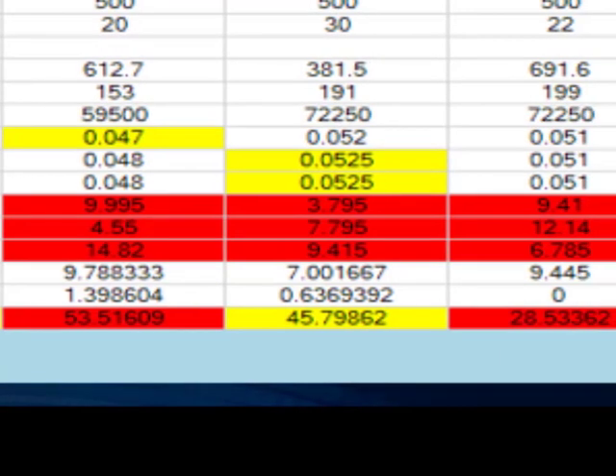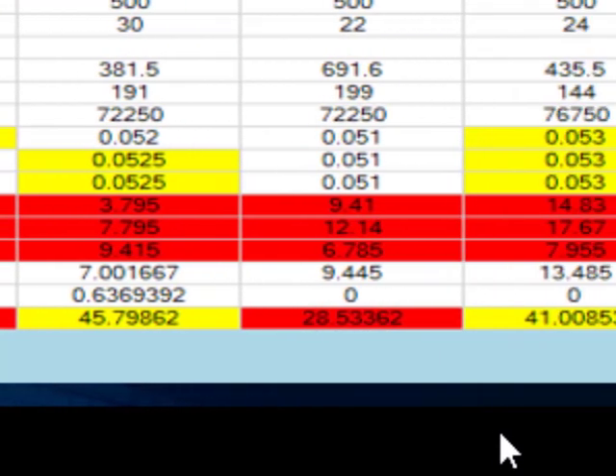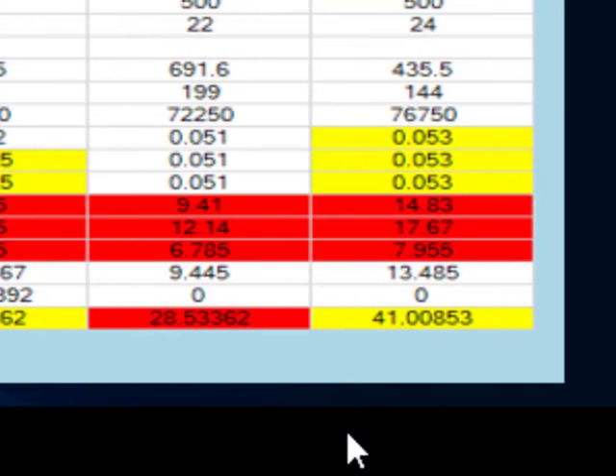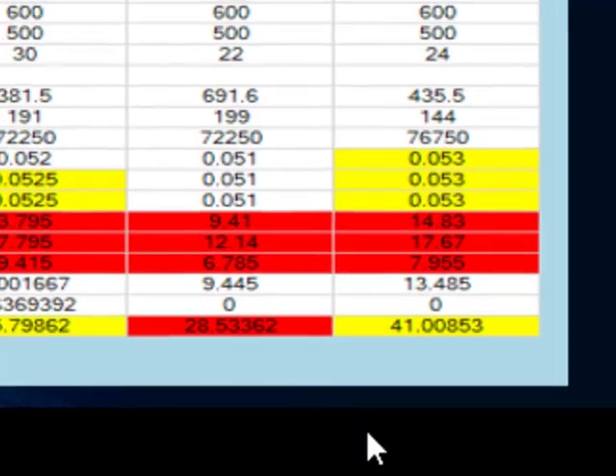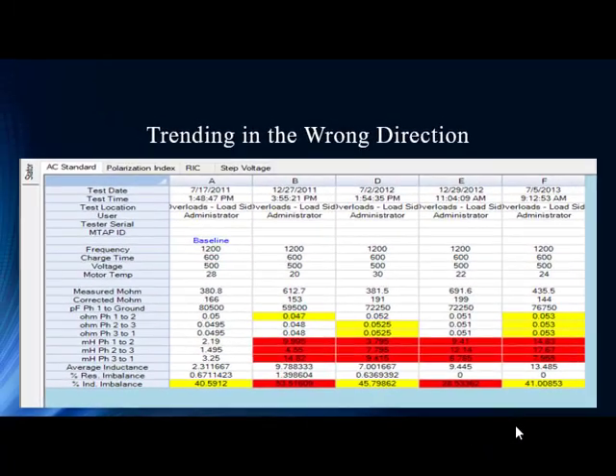Even in caution — it's shown in yellow caution on the left column — that deserves an alarming situation and certainly deserves a lot of attention. We would recommend doing a rotor influence check immediately, separating between the rotor and the stator, and correlating with online testing if at all possible. What they decided to do is increase the frequency of testing, which is something we do recommend.